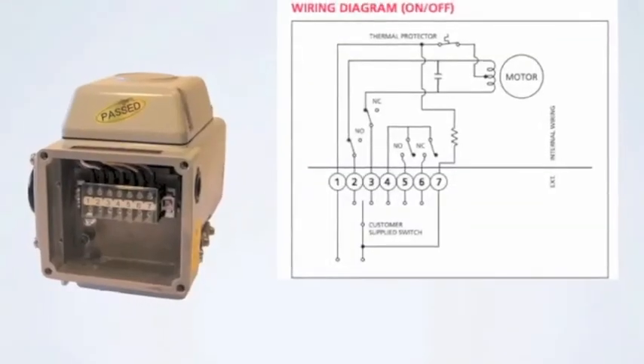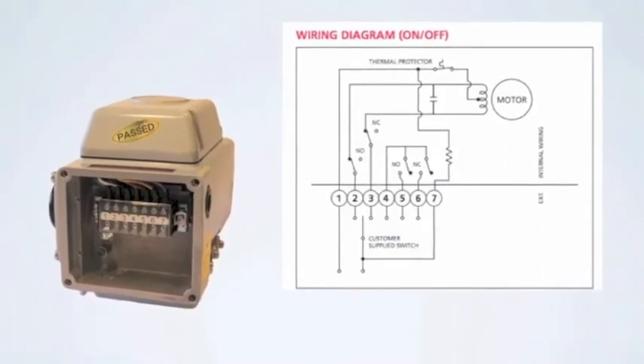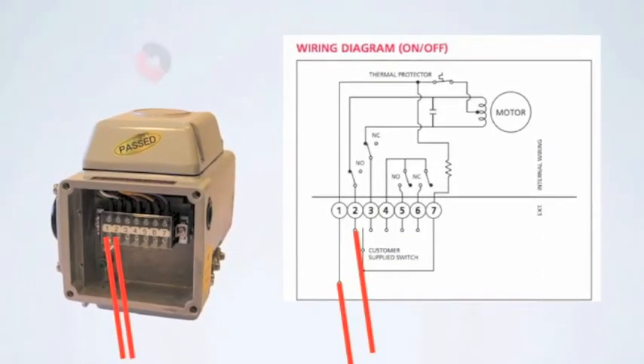To open or drive the actuator in the counter-clockwise direction, apply power to Terminal 1 and Terminal 2. The actuator will turn counter-clockwise until it reaches the internal limit switch and shuts off.